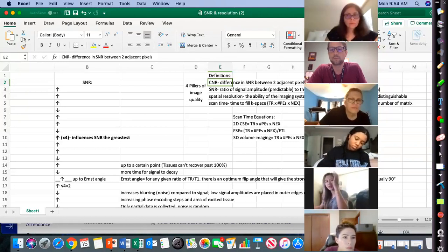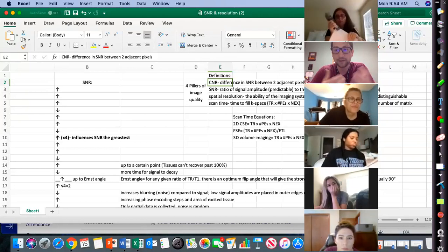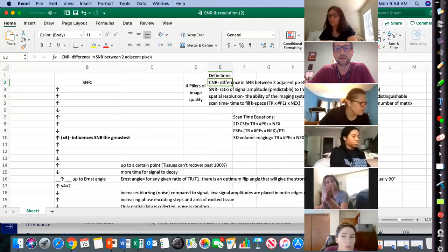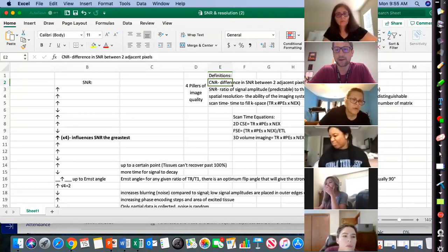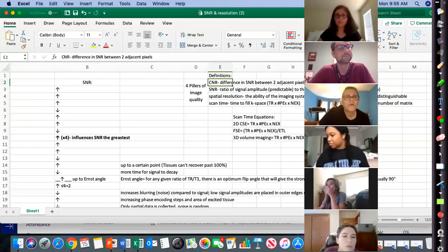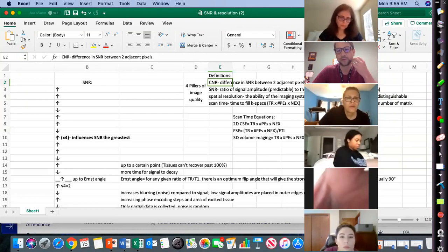From the patient, but it's random. Okay, the patient's one place where you get noise, but also the environment, the room environment, so the scan room, the zone 4 room environment. That's where noise could come from. And also the system, so your MR system. The bore of the magnet could also produce noise on your image. So those are the 3 things where noise can generate from: the patient, your system, and even just the room environment.